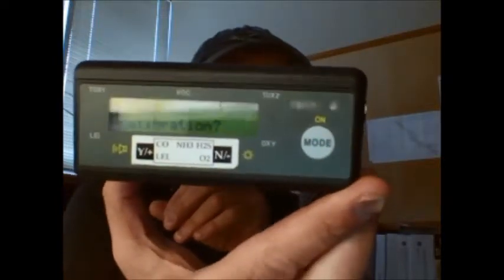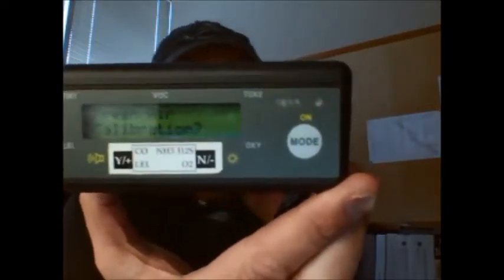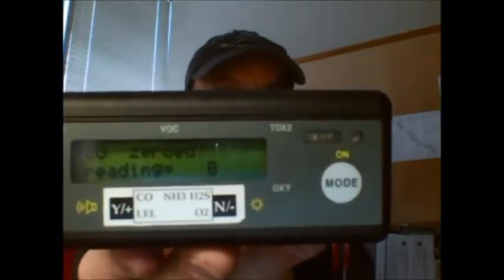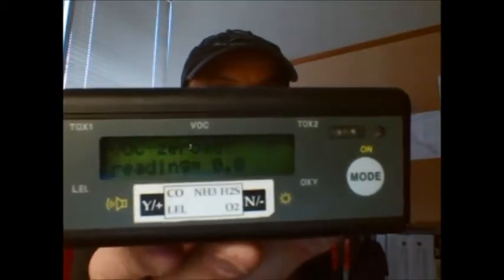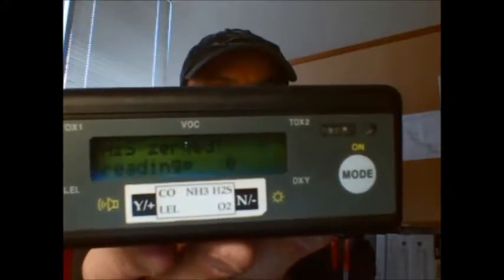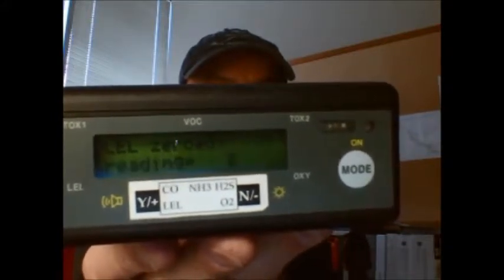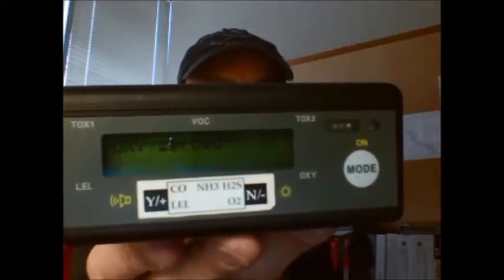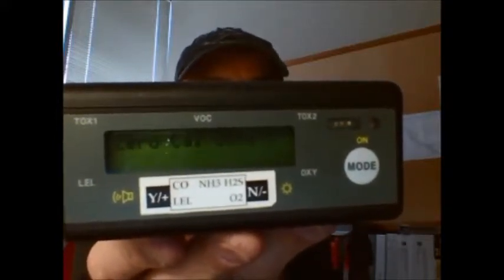So now it's finished its boot up. The first thing it asks for is a fresh air calibration. So we do want a fresh air calibration, and all we do is we push the Y button, which stands for yes, and it'll go through a zeroing process. So it will zero all the cells in the meter. As you can see, O2 20.9 is the air.